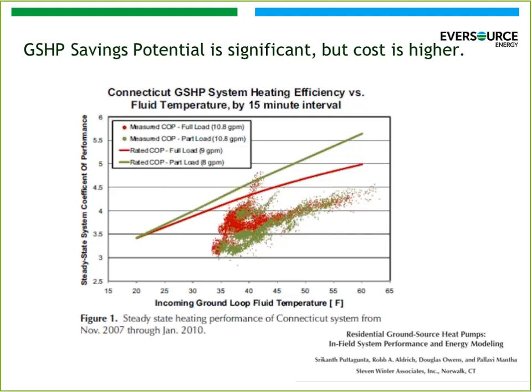I want to caveat that though, and the rated COP isn't always necessarily what you're going to get out of the unit. There's a lot of design factors to consider, in terms of making sure that your ductwork is designed properly, that if you're installing a ground source heat pump, your ground loop is installed and sized properly, and if you have a ductless heat pump, you don't want to leave it outside on the ground where it might get buried with snow, otherwise it's really not going to perform at all. So there's a lot of different parameters that have to be considered when you're comparing rated efficiency versus the actual efficiency.